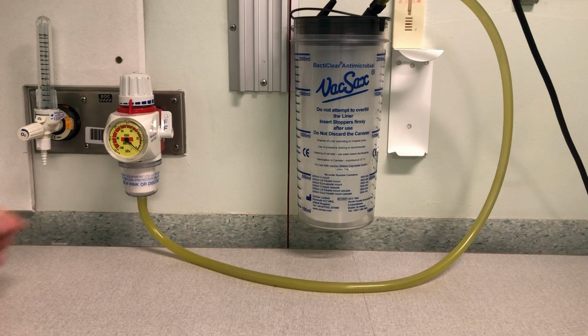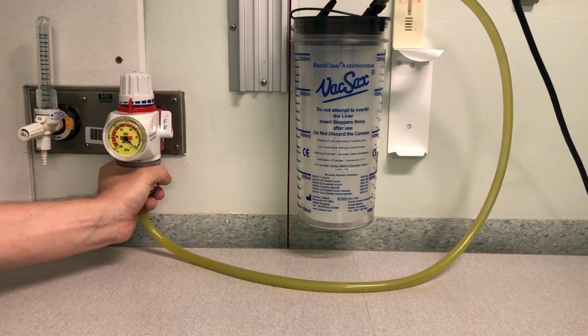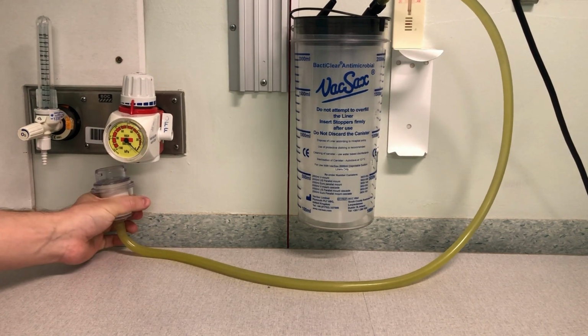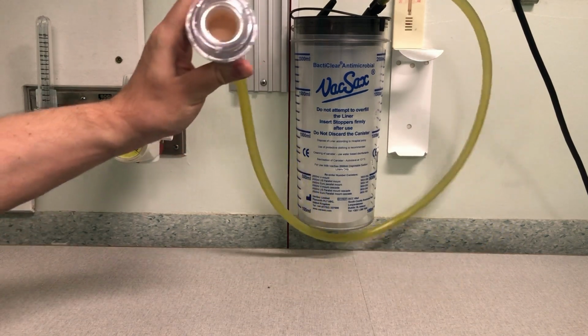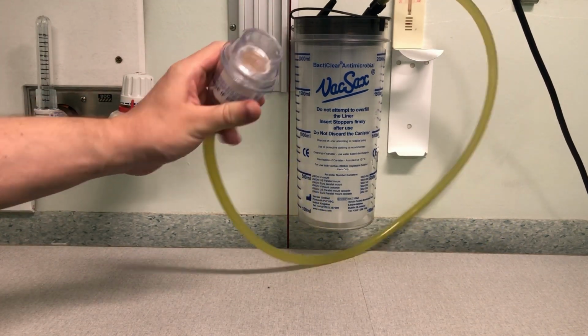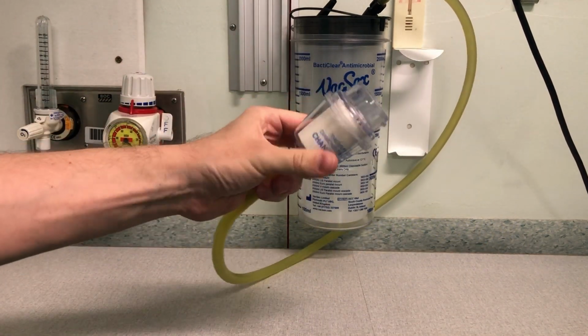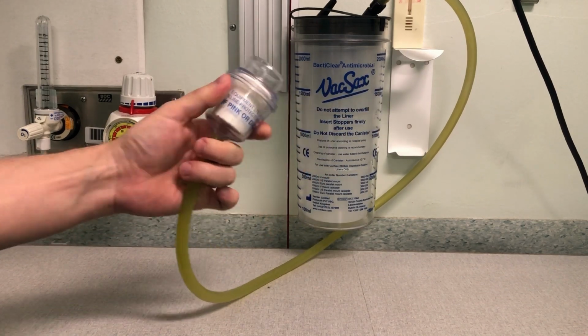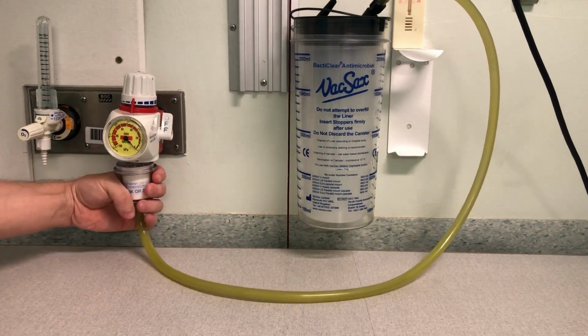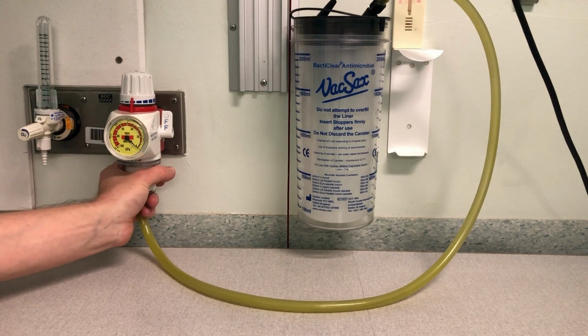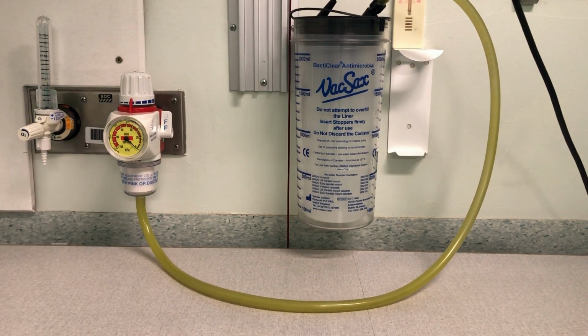So, changing the filter. The filter gets changed as per local policy. For us it's yearly, hence why we do yearly on the tubing as well. Or when the filter is discoloured or turns pink. And to change the filter, simply twist the filter off and twist in a new filter. When to change the suction canister liner: typically change the liner when it's over half full, between patients, or as per local policy.